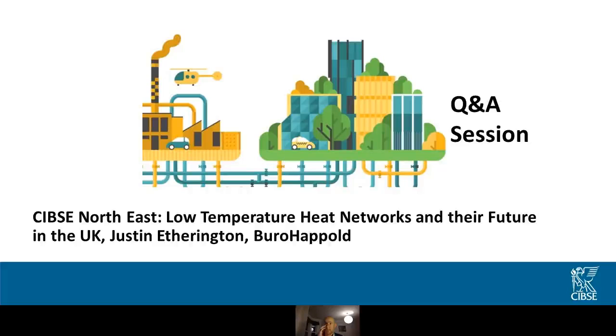On the question about cascading: yes, there are a number of ways to look at it, but we were trying to reduce space heating temperatures as far as possible, then having domestic hot water booster top-up pumps on the back of the space heating circuit, in that cascade configuration. Really what you're trying to do is drive supply temperatures down as far as possible.